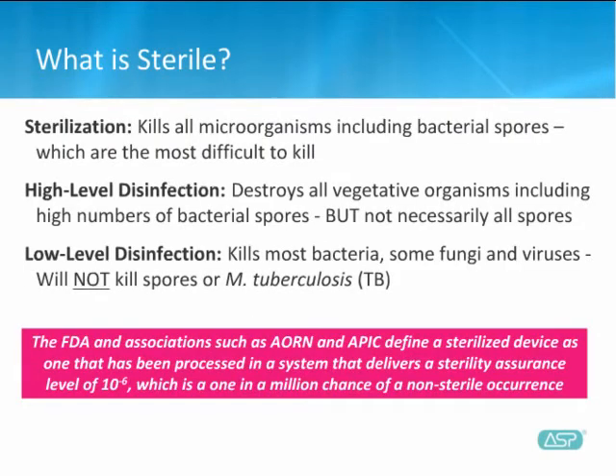I sometimes hear the terms disinfection and sterilization used interchangeably, which is very concerning to me. This is incorrect and very misleading. In basic terms, sterilization is the destruction of all microorganisms, including spores. HLD can be anything less than that. In the operating room, these differences are critical and can mean the difference between life and death.